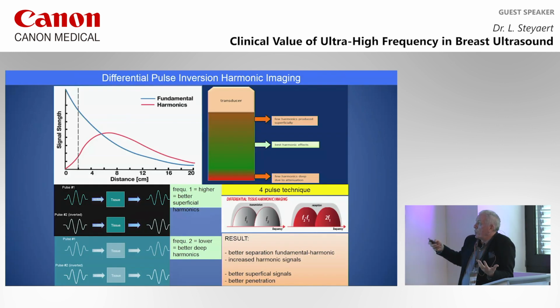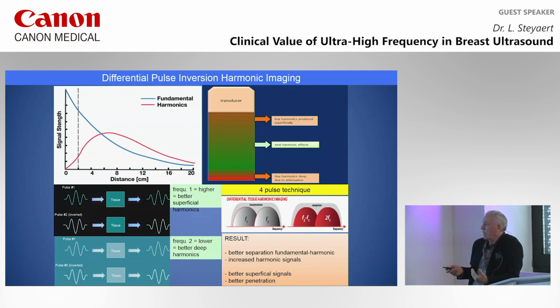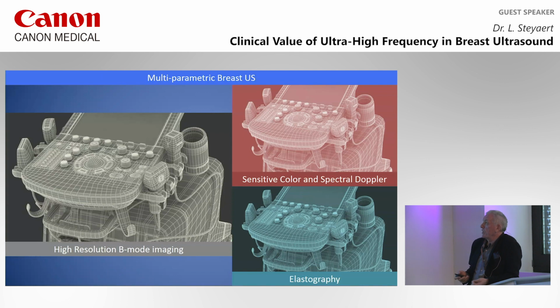To improve all this, I will not go into detail, but we now have pulse inversion harmonic imaging. We have 2 pulses which are each other's mirror image. By adding the returning signals, we get a better signal, because we get rid of the artifacts. The artifacts are from the linear responders, so they have the same frequency, and we can cancel them out and add the harmonic signals, which are asymmetric, so we have a better signal. To improve this for superficial and deep at the same time, we use a technique with 2 times 2 pulses. For the deeper regions, we get better penetration, and better resolution in the superficial. That's the result of this pulse inversion differential harmonic imaging.